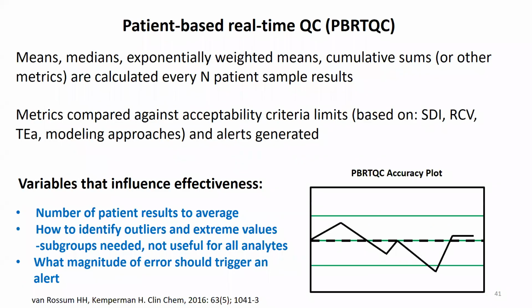Another tool for preventing errors is the use of patient-based real-time QC. In this approach, the laboratory's reported patient sample results are monitored in real time to detect potentially developing performance issues. If the analytical measurement system is performing as expected, and the analyte is stable in the patient population tested, then the average of patient results should stay the same over time. A trend in the results could indicate a quality issue.